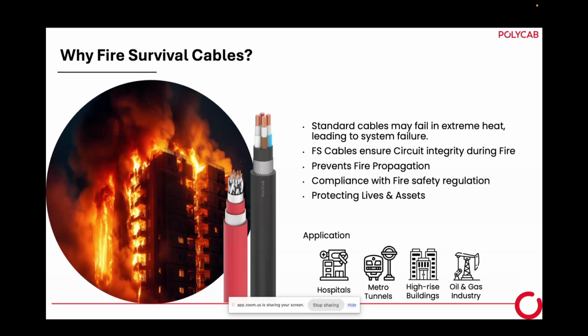FS cable has the property of circuit integrity up to 950 degree temperature. It does not evolve toxic gases and dark smoke, and it has a low heat release rate, meaning when it burns, heat does not release much, so the balance part of the cable body does not get heated by the flame. This prevents fire propagation, ensures compliance with fire safety regulations, and protects lives and assets.